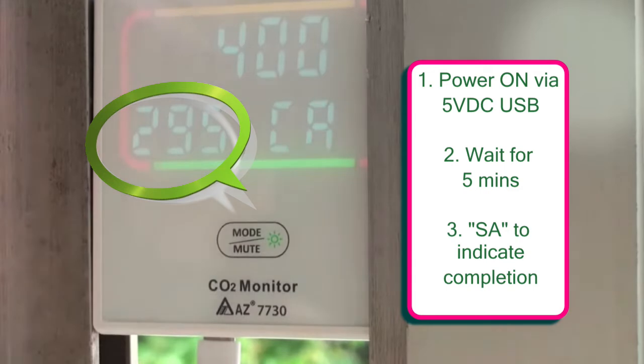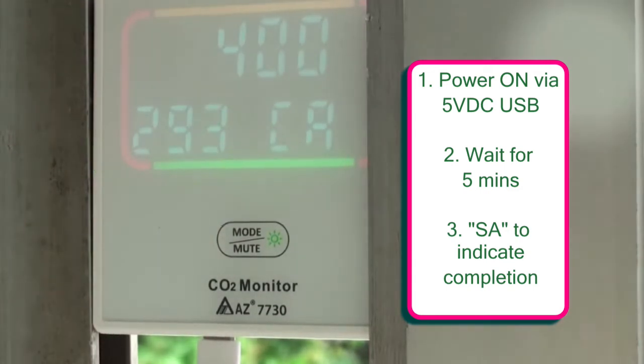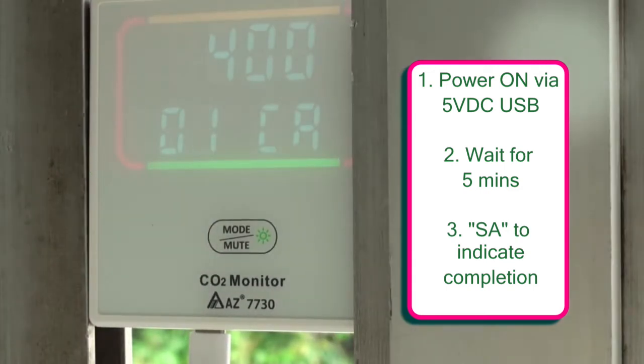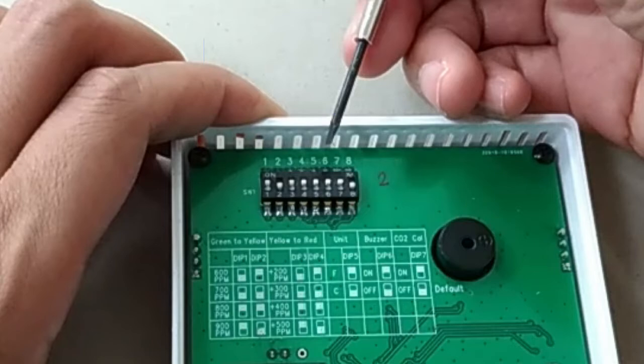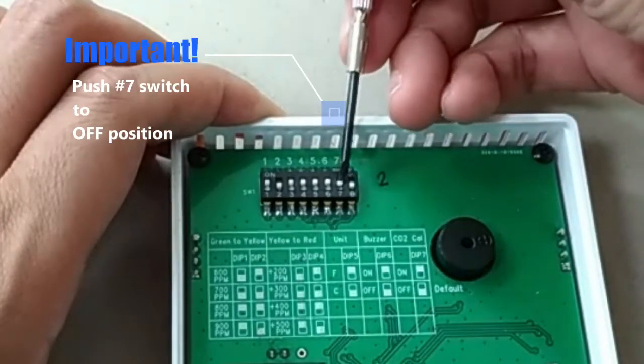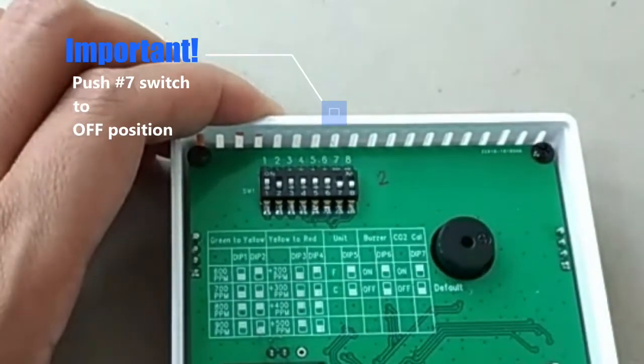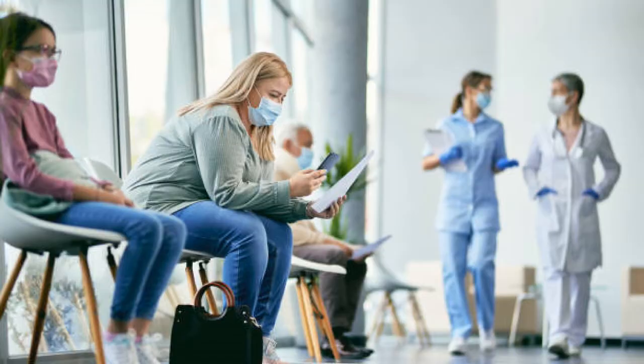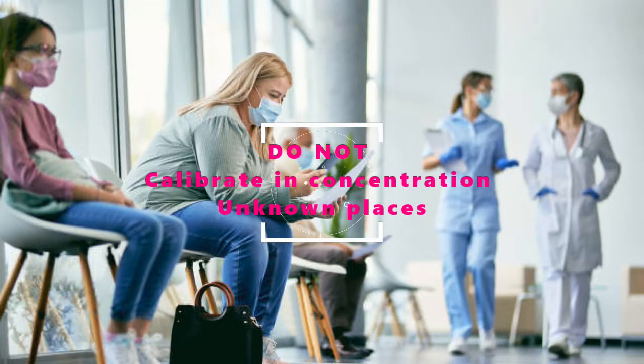Keep distance from the monitor to avoid the exhaled CO2 affecting the calibration result. After the 5 minute countdown, SA appears on the display to indicate the calibration is saved. Remove the power supply and push the number 7 dip switch back to the off position to end the calibration. Do not do the calibration in unknown CO2 conditions. Otherwise it will be taken as 400 ppm and lead to an inaccurate result.